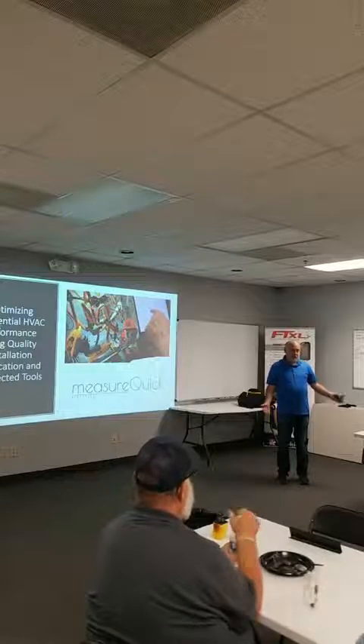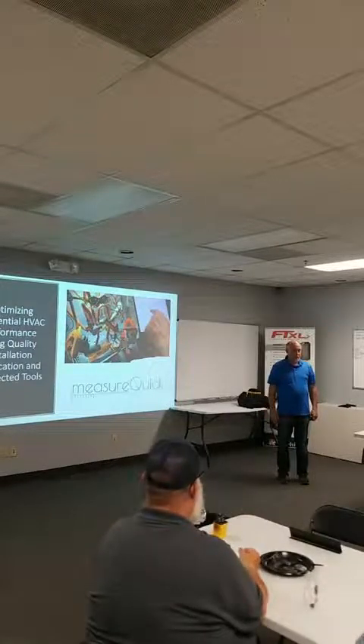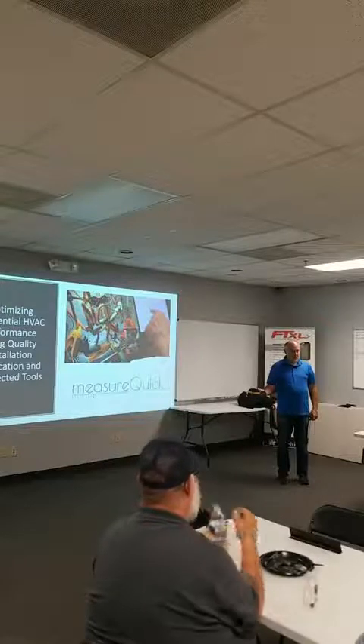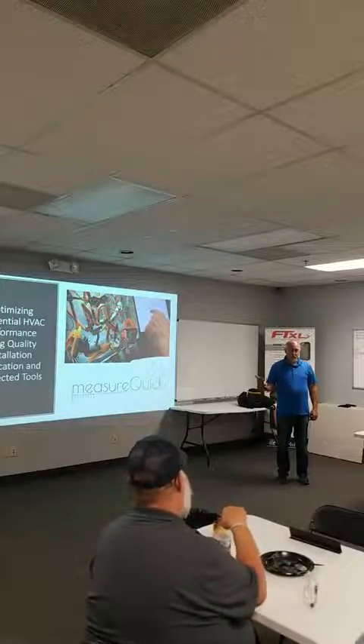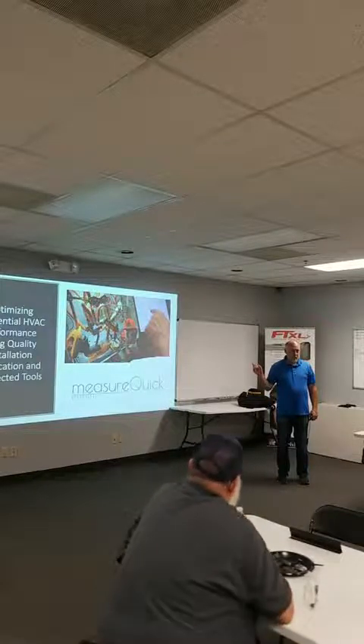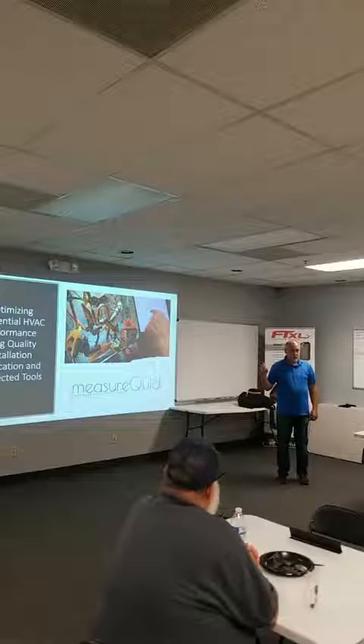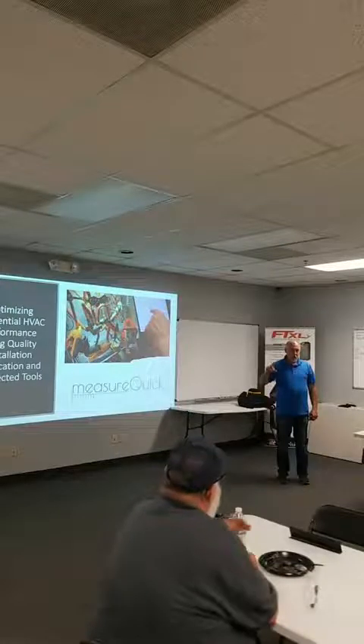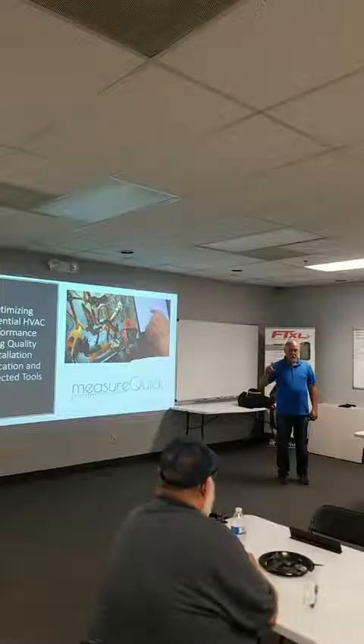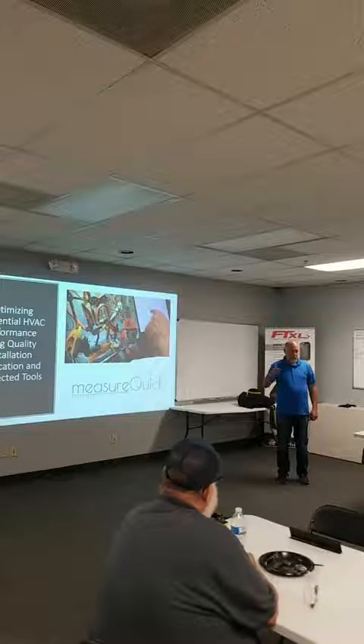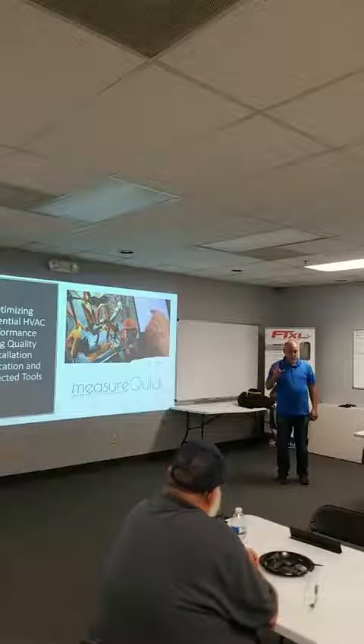If you don't know, nobody ever showed you how to do your job for a living. I found out 15, 16, 20 years in that I had no idea what I did for a living, because I had no idea how that equipment should run. The whole epiphany came from this temperature pressure chart. On the back of it, it had TD, temperature difference, for different refrigeration applications, and I noticed it was always the same. I thought, why isn't it the same for air conditioning? I found out it sort of is, except it's a little variable because we can have 350 CFM a ton, or 400, or 450. But it's always a function of the duct design, so the only way you find the true TD is to measure it, but it does fall in a certain range.